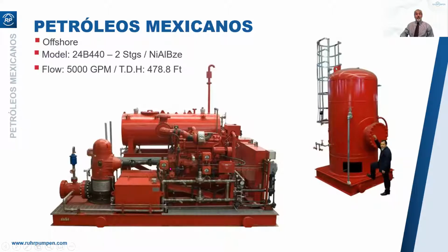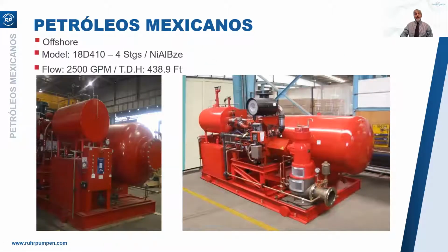Now here's a pump system with a primary start system, which is electrical start with batteries in these battery boxes here underneath the drive shaft. But here is the pneumatic backup start, and you get some idea of the size of a pneumatic starting system. And that's why they're not quite so popular offshore, just because of this sheer size. And we see the same thing here again. I mean, here is the diesel tank, and beside it there is the air accumulator for the pneumatic start.